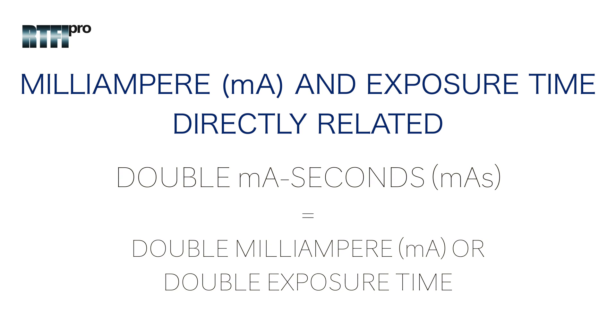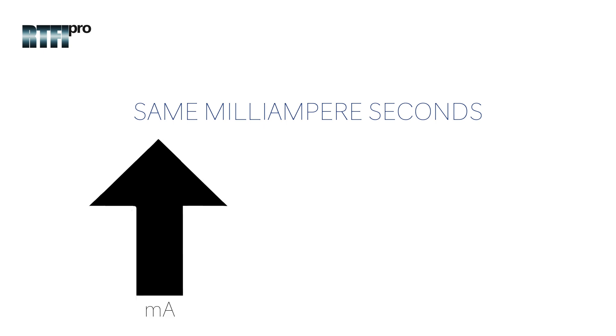Milliampere seconds can be doubled by doubling the milliampere or by doubling the exposure time. A change in either milliampere or exposure time proportionally changes the milliampere seconds. To maintain the same milliampere seconds, the radiographer must increase the milliampere and proportionally decrease the exposure time. For example, if the original exposure was set at 10 MA and an exposure time of 10 seconds, it would be a 100 milliampere second exposure.